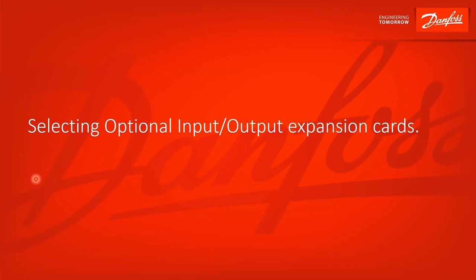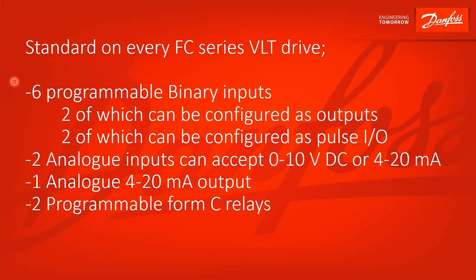How to select optional input-output expansion cards? Let's start by going over what comes standard in every VLT drive. You've got six programmable binary inputs. Two of those can be configured as binary outputs, and two can be configured as pulse inputs or pulse outputs. You've got two analog inputs that can take either 0-10 volt or 4-20 milliamp. You have one analog 4-20 milliamp output and two programmable Form C relays.